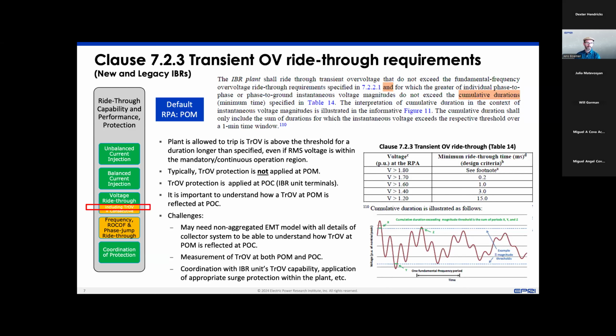Now, typically for transient overvoltage, if you use protection, then that protection is not applied at the point of measurement, but it is applied at the point of connection, which are the IBR unit terminals, in order to protect the inverters from damage. That said, throughout the plant, you might use surge arresters or other means in order to coordinate some of the transient overvoltage. And therefore, the protection applied at the unit level needs to be coordinated with other elements throughout the plant.